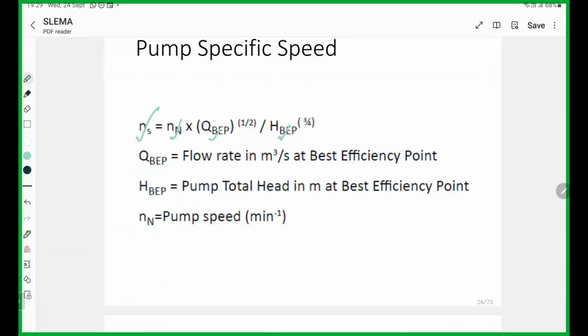The important thing is the flow rate, okay. The head, this one is the per-impeller head, very important. You have to keep in mind this head is the per-impeller head. If the head is 50 with one impeller, you can use that head as 50. If it's a multi-stage pump, if it's a two-stage pump, then you have to use 25 for this equation. You have to keep that in mind.